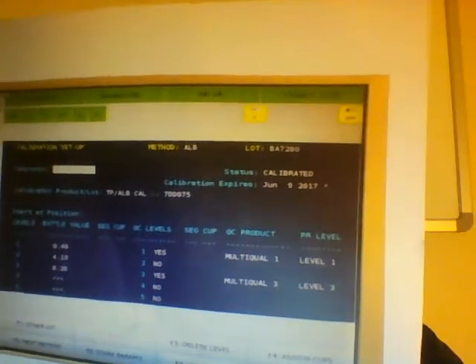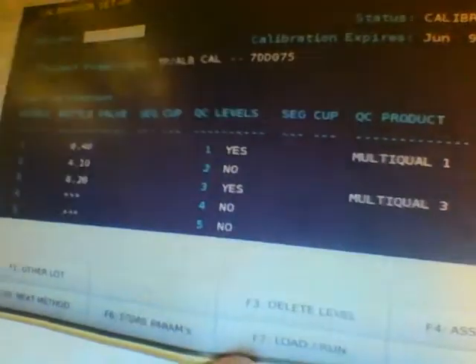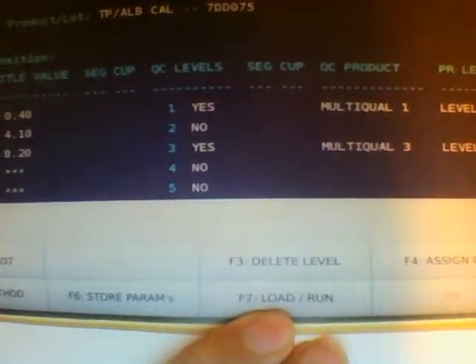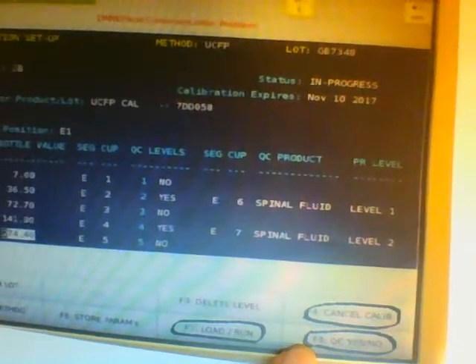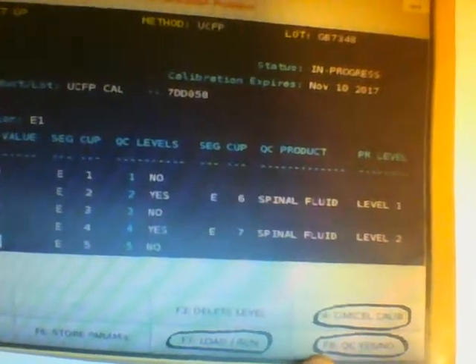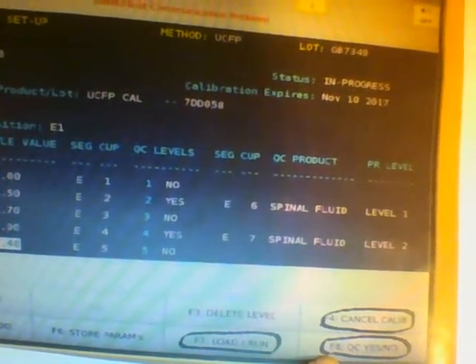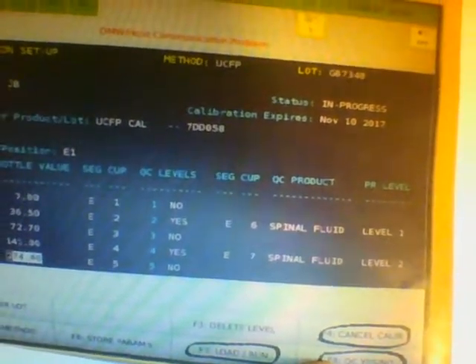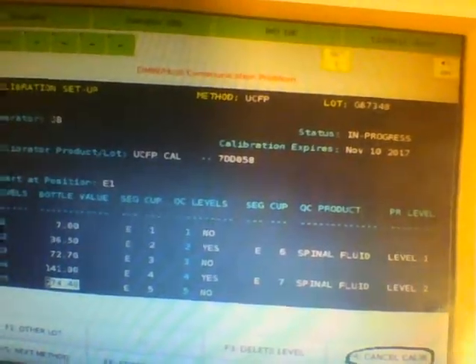So once you've put that up there and you've put everything in the right cup and everything looks correct, you push F7, load and run. Now sometimes on some calibrations, not all, depending on how your supervisor sets it up, some calibrations automatically have QC, others don't. So if they don't automatically have QC, you can push F8, QC yes or no. But once you have chosen F4, assign cups, you no longer have these menu options. But this is an option, I just wanted to show you.